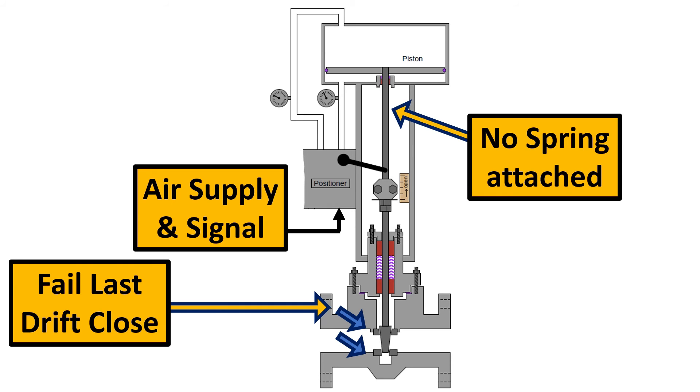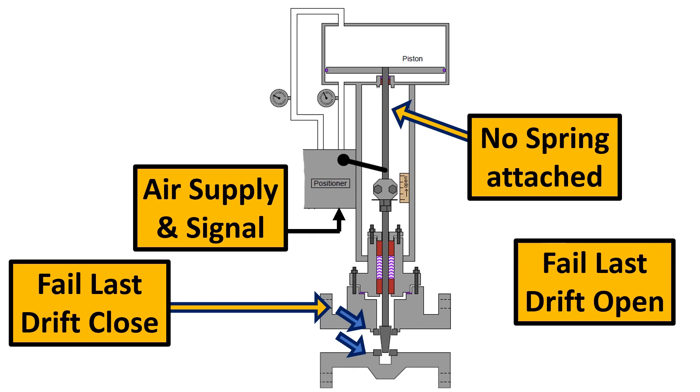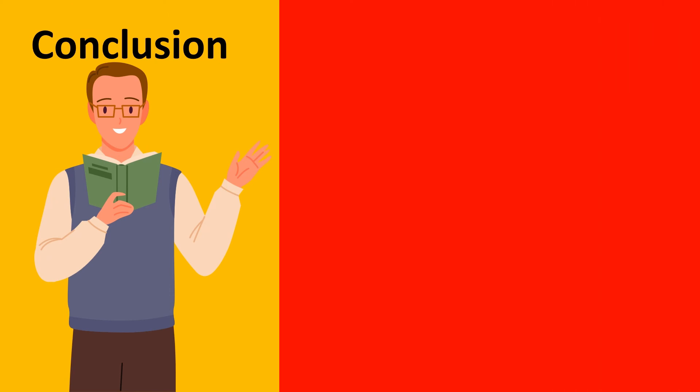So just as in, this is a hypothetical drawing but an example is basically the fluid flow is going to assist the plug to get to its failure close mode if it is a globe valve. Similarly, the fail last drift open, the fluid flow will assist the plug to get into its open position. So eventually the valve will either open which is drift open or close which is called as drift close.